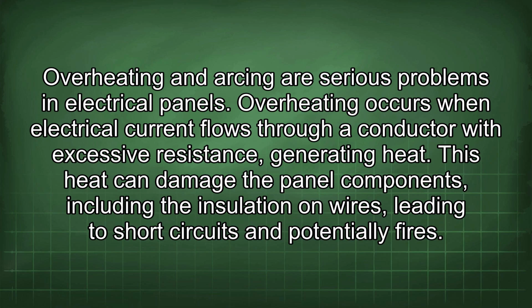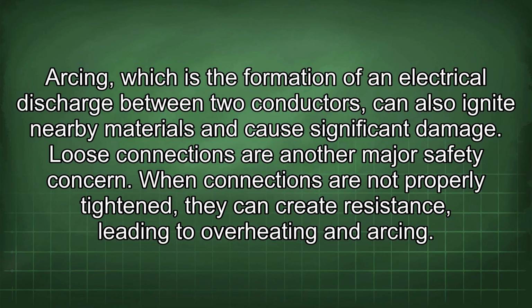Overheating occurs when electrical current flows through a conductor with excessive resistance, generating heat. This heat can damage the panel components, including the insulation on wires, leading to short circuits and potentially fires. Arcing, which is the formation of an electrical discharge between two conductors, can also ignite nearby materials and cause significant damage. Loose connections are another major safety concern.